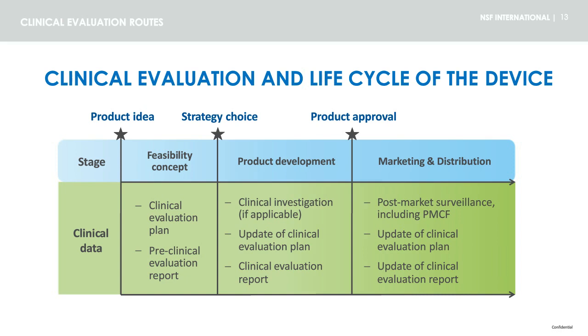During the product development, it is the time to perform tests to acquire preclinical data showing the performance and safety of the device. In the case of implantable Class 3 devices, as well as Class 1 or 2 devices for which there is not sufficient clinical data available, it is also the moment to perform clinical investigations.